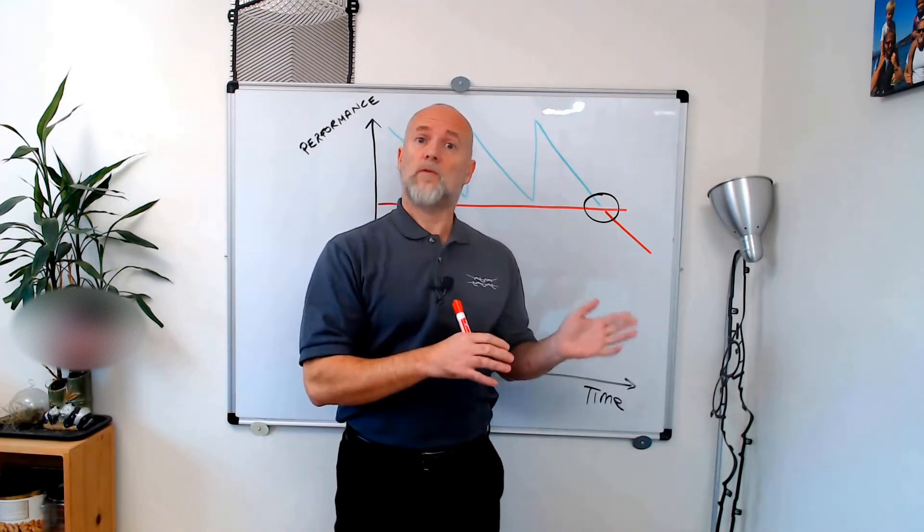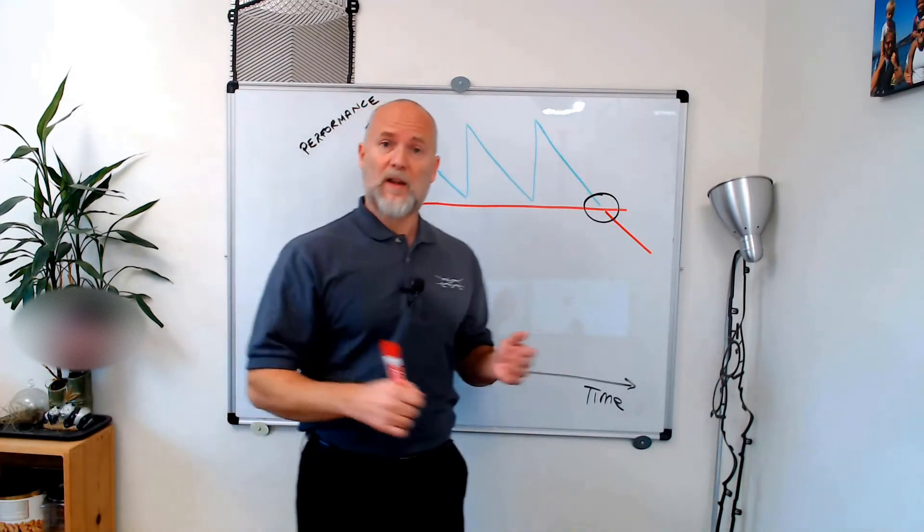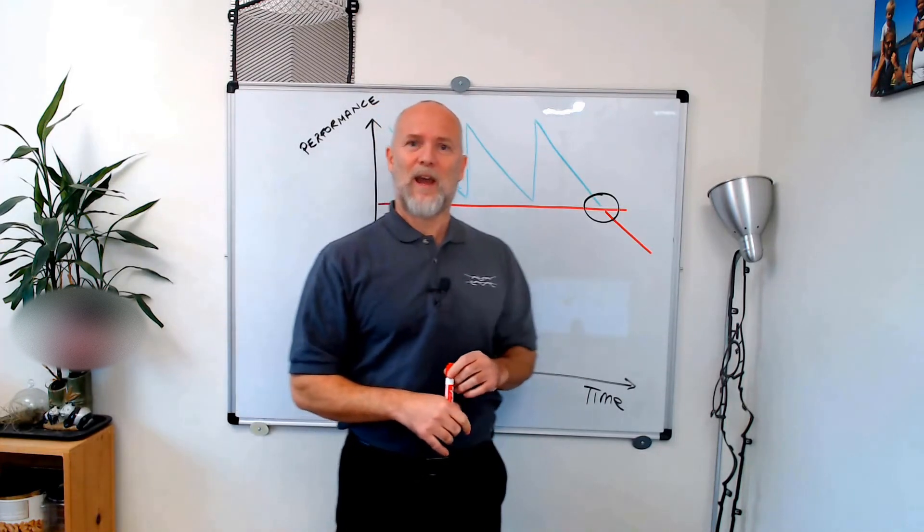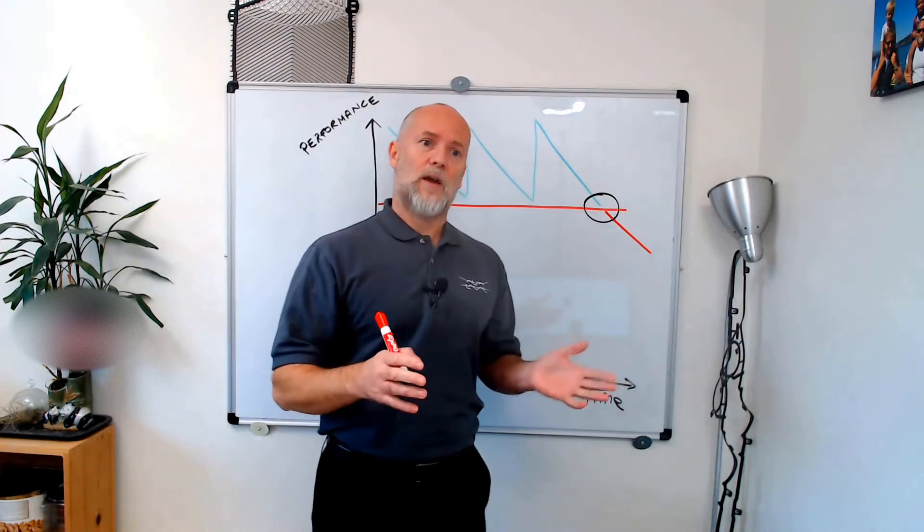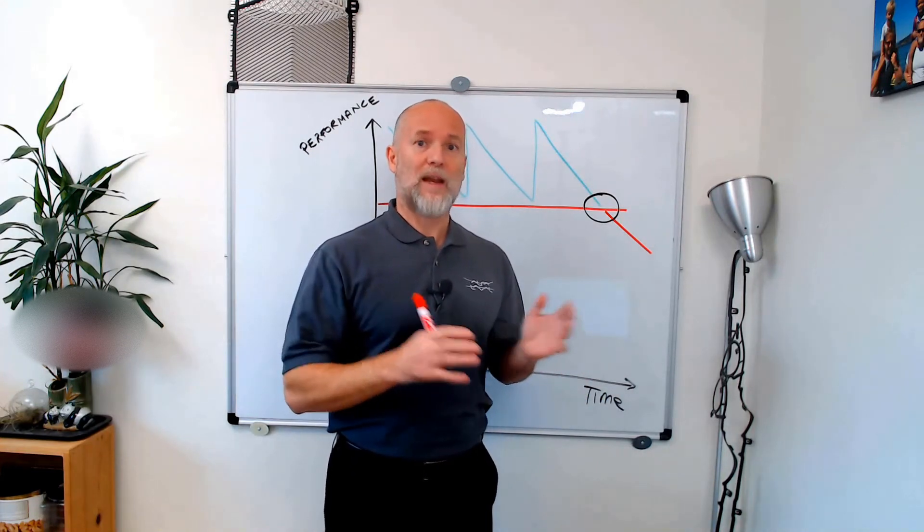So in the previous two videos we looked at when is the right time to actually open and check a heat exchanger and we said never. You are not supposed to actually open heat exchangers just to check it. You are supposed to open heat exchangers if you really have to, if you need to do a mechanical cleaning.